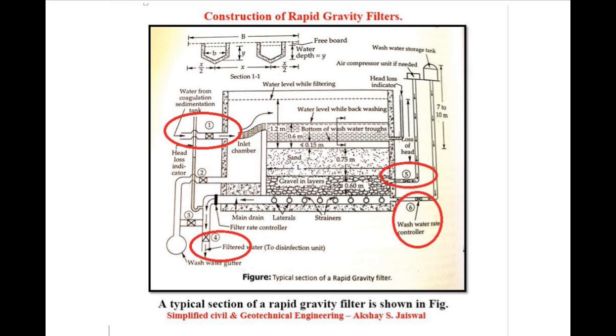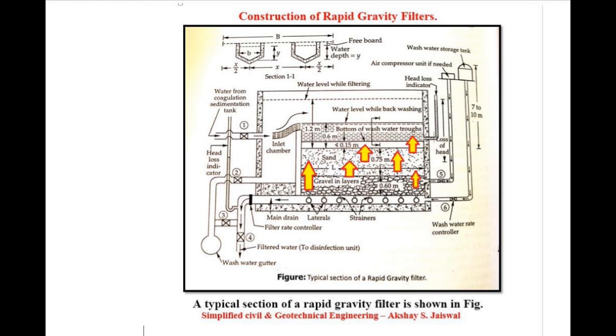Valves 1 and 4 are closed and valve number 5 and 6 are opened. Shurvaat mein valve number 1 aur 4 ko band rakha jata hai aur valve number 5 aur 6 ko khola jata hai. The wash water and compressed air are thus forced upward from the under drainage through the gravel and sand beds. Wash water aur compressed air ko under drainage mein maujood gravel aur sand se hote hue upar ki oor force kiya jata hai.